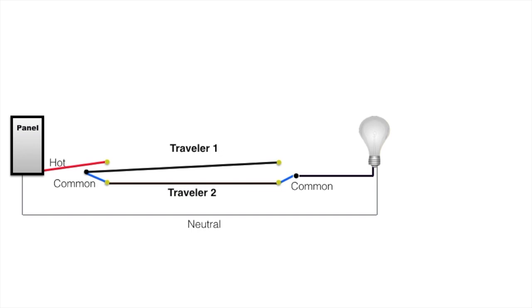And this, by the way, is when you're checking a three-way circuit that you have just hooked up, don't be satisfied with just throwing one of those switches and having the light go on. It doesn't necessarily mean you did it right. Run down to the other one. Operate that one. Make sure things happen. Then run back to the first one. Operate it again. Make sure everything acts the way it should, no matter what position the switch is in. If you hooked it up wrong, you're going to find out pretty quick.